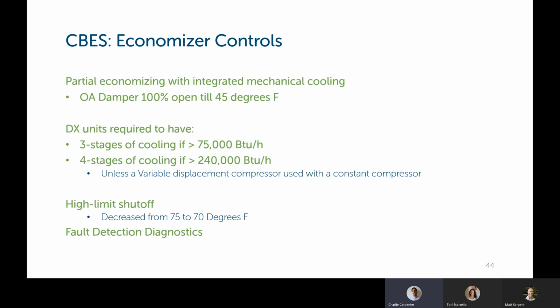And if you've got direct expansion cooling units, if they are greater than 75,000 BTU per hour, you need to have at least 3 stages of cooling, and greater than 240,000 BTU per hour, they must have at least 4 stages of cooling. An exception to that is if you have a constant speed compressor and then an additional variable displacement compressor or compressors that could modulate the load as needed.